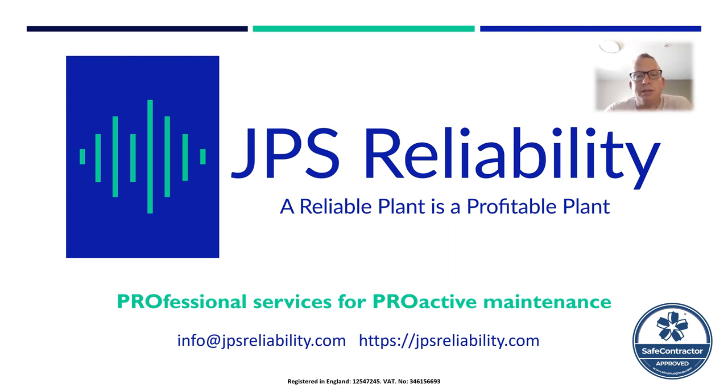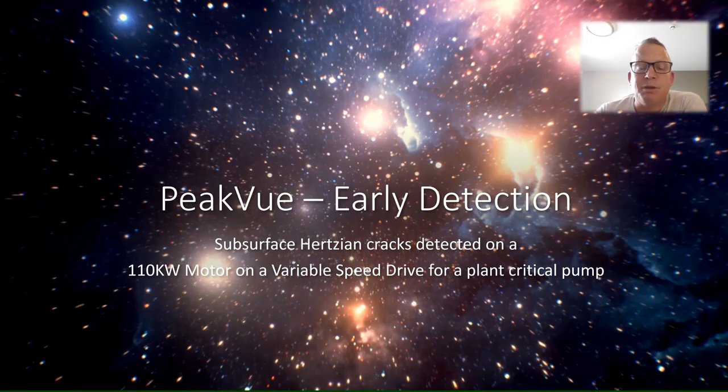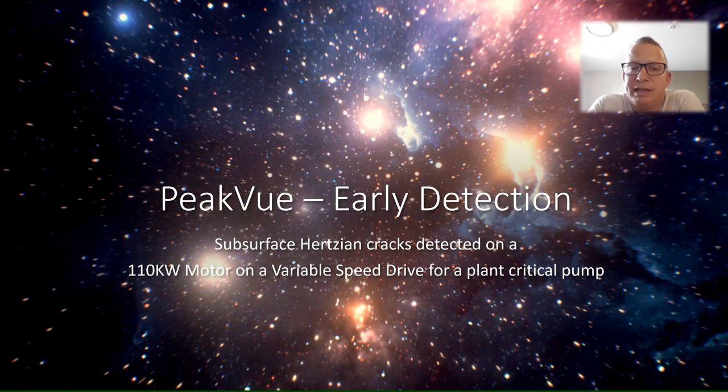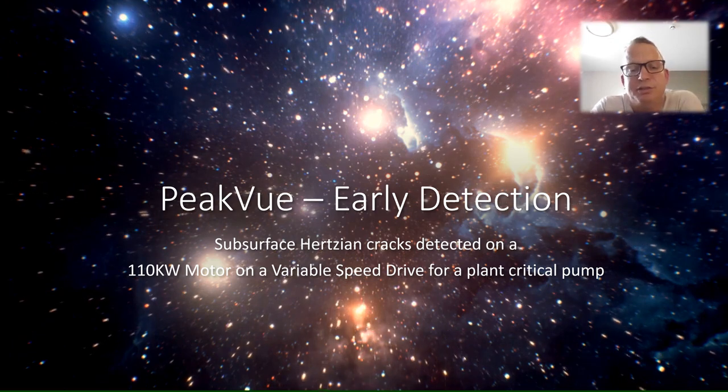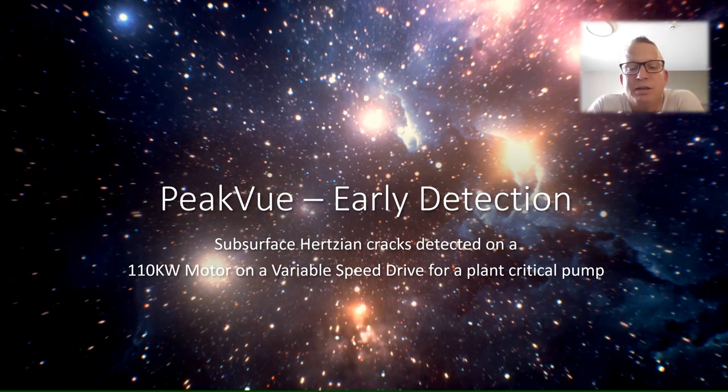And what we're going to go through today is the PeakVue technology. Just to highlight, when PeakVue is used correctly with good setup, you can pick up the subsurface cracks. So this is early detection, hence why we got the screenshot of the universe starting. So we're looking at where we can pick up subsurface Hertzian cracks.